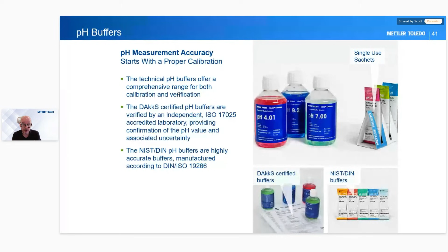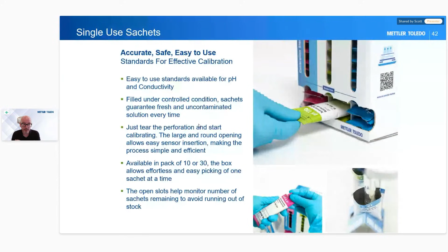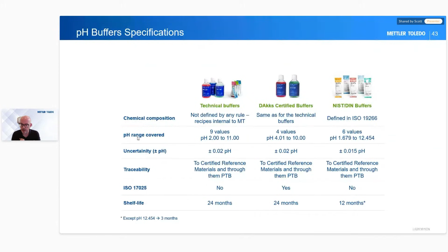The other ones we do are our NIST and DIN buffers. It depends on what kind of measurements and what kind of system you use, but we also do NIST and DIN buffers in bottles and sachets. This is more about single-use sachets. Here we have dispensers showing them off. They're available in packs of 10 or 30, depending on what you need to do. What this really does is improve your accuracy when you're taking calibrations, because it's sealed inside there and it's single use, and when it's done, it's thrown away as well. This is a list of everything we've got, with different values, and the uncertainty here is plus or minus 0.02, as we talked about before. Different ones have different shelf lives.